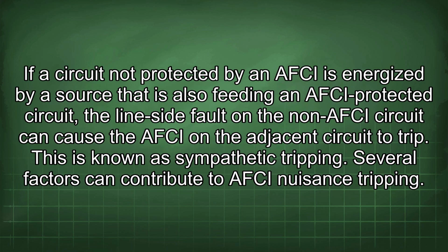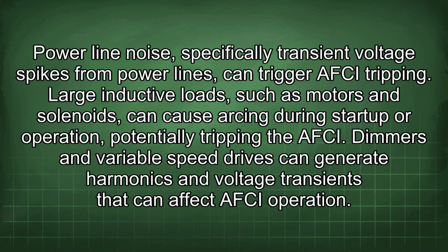If a circuit not protected by an AFCI is energized by a source that is also feeding an AFCI-protected circuit, the line-side fault on the non-AFCI circuit can cause the AFCI on the adjacent circuit to trip. This is known as sympathetic tripping. Several factors can contribute to AFCI nuisance tripping. Power line noise, specifically transient voltage spikes from power lines, can trigger AFCI tripping.